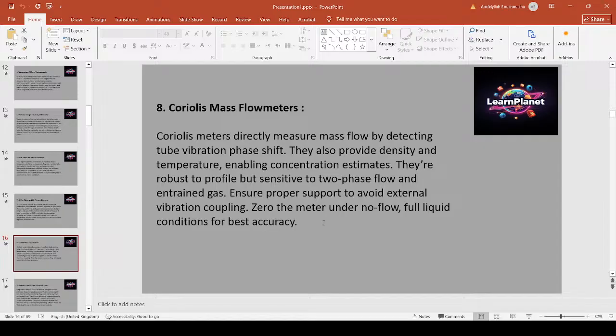Coriolis mass flow meters. Coriolis meters directly measure mass flow by detecting tube vibration phase shift. They also provide density and temperature, enabling concentration estimates. They are robust to profile but sensitive to two-phase flow and entrained gas. Ensure proper support to avoid external vibration coupling. Zero the meter under no flow. Full liquid conditions give the best accuracy.